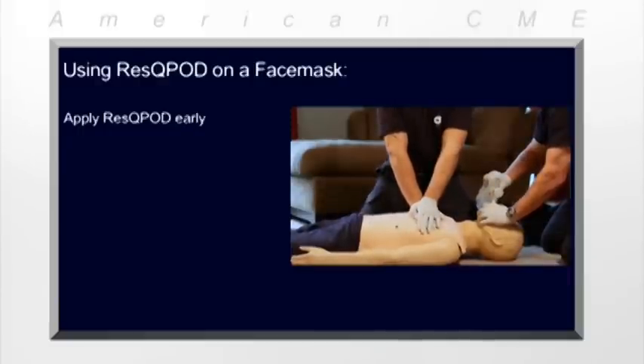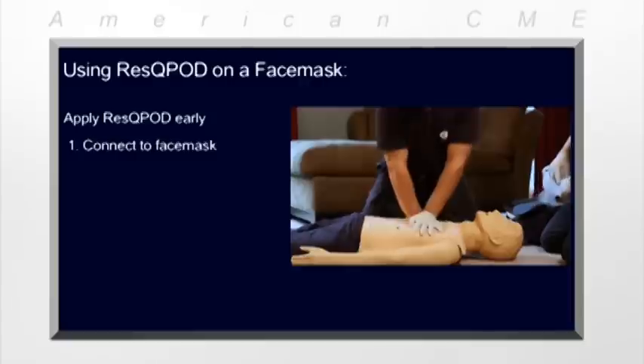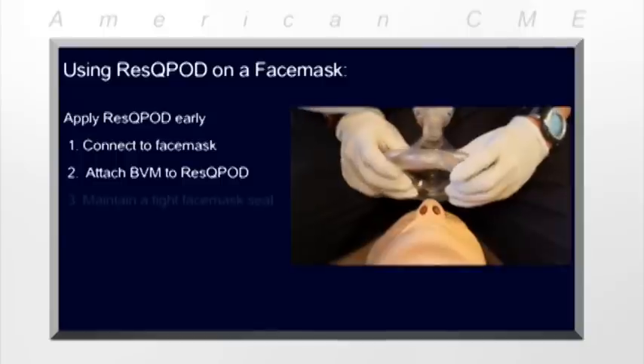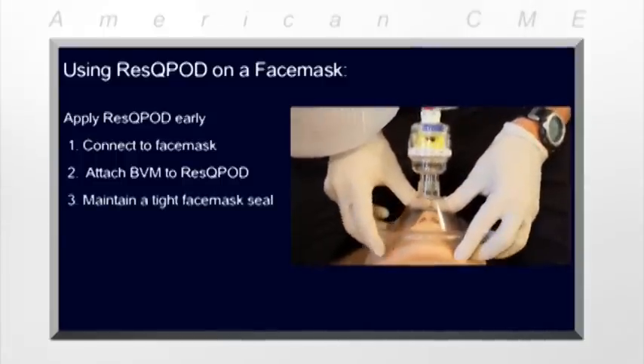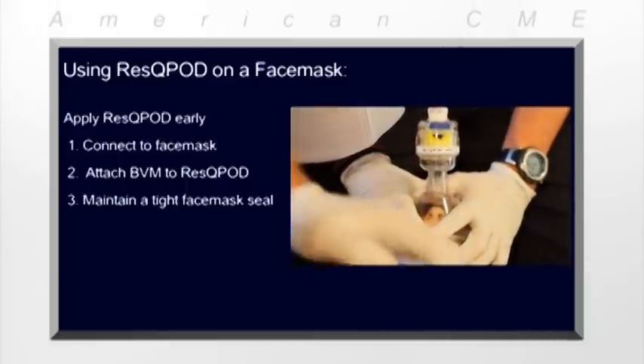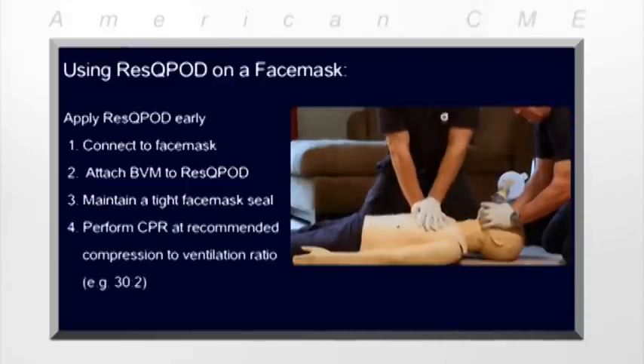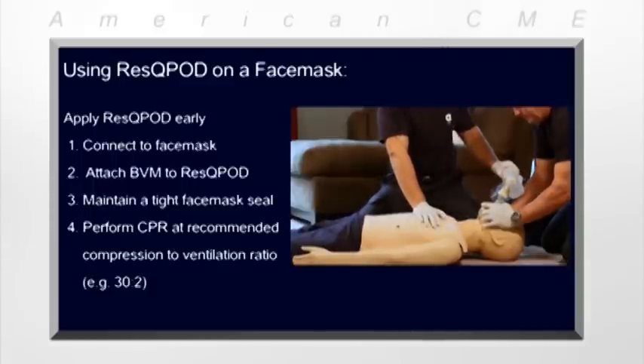Applying the ResQPOD as soon as possible after compressions begin allows the patient to get enhanced circulation early in the resuscitation effort. To use the ResQPOD, first connect it to the face mask, then connect the ventilation bag to the top of the ResQPOD. Next, open the airway to establish and maintain a tight face mask seal on the patient's face. Use a two-handed technique to assure that no air can be drawn in from around the face mask. Then begin performing CPR at the recommended compression to ventilation ratio. It's best if the airway person's only job is maintaining a face mask seal.